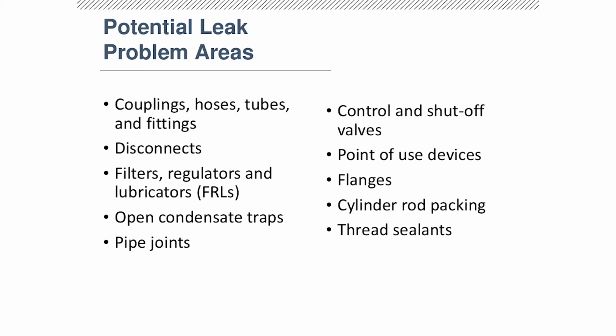So these are potential areas where you're going to see leaks. You'll have a lot of those. Some of the pneumatic stuff is a built-in leak. Because how does a bimetal thermostat work? It reduces the pressure, so you can open a valve and it puts it back on. So it's kind of a built-in leak anytime you have a pneumatic system that uses air for controls.